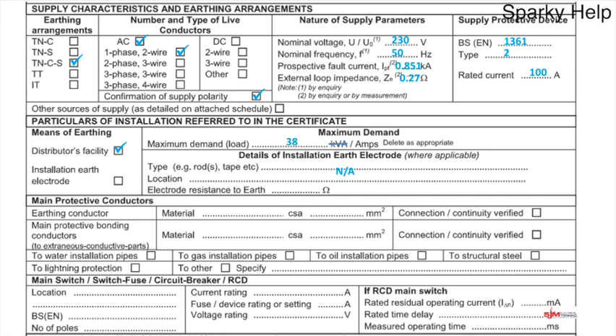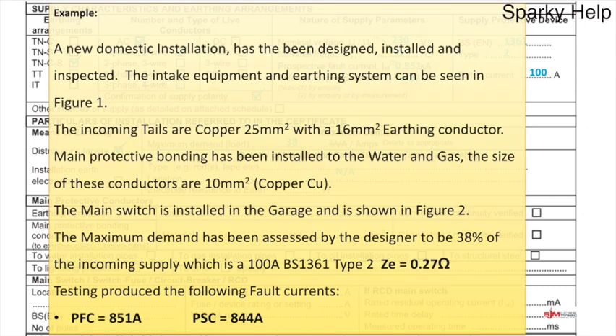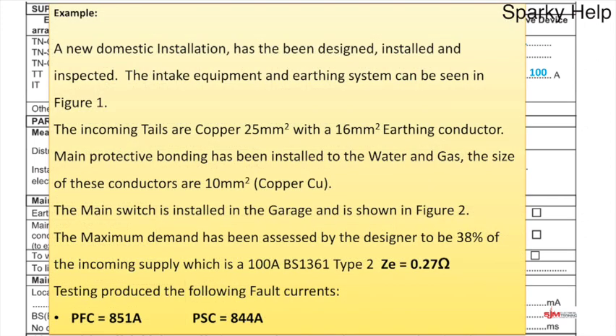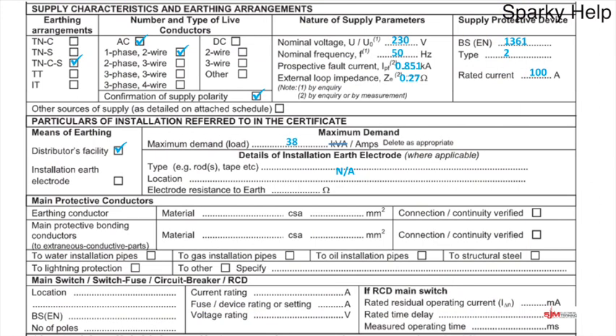Details of installation earth electrode, but we've just said there aren't any, so we won't bother putting anything there. So that's not applicable. Now the next bit talks about bonding and cable sizes and earthing conductors in general. Bizarre, isn't it? We don't put the size of the tails in. Obviously we've put it in here, but we've got the earthing conductor is a 16mm, and we have main protective bonding to the water and gas, which are 10mm, and they're all copper conductors. So let's see what we can do. Earthing conductor, the material is copper. The size was 16mm. The bonding conductors were copper. The size was 10mm. What did they go to? Well, it said the water and the gas.